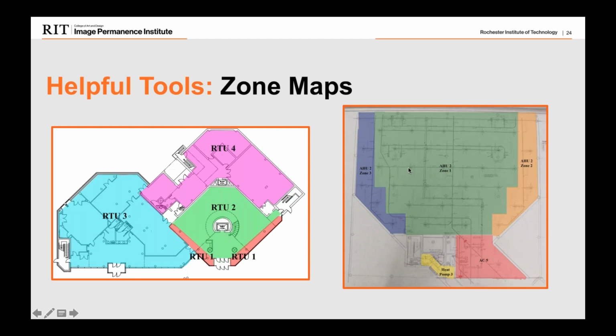A similar scenario can happen in a room with 3 zones from one unit. Say zone 1, the large green zone, were to fail, or the reheat fails, we'll have cold air coming out in that zone. The blue and yellow zones on either side will have to compensate and push really warm air in, so the unit works hard on both ends to make up for the middle not working, resulting in inefficient operation on those ends as well.